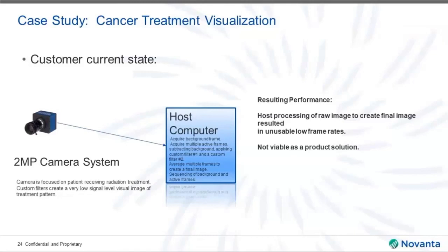And so there was a bunch of image processing algorithms that we did that were done first on the host computer. You acquire a background frame, you acquire multiple active frames of image data that include this signal that is a radiation and see where it's hitting the patient. You have to subtract the background frame and apply a couple of custom filters actually, and several operations in that. And those custom filters are there to reduce the noise. It's a very noisy signal, and to intensify the signal of the radiation, what you want to visualize. And then do some frame averaging again to reduce noise and to increase the signal level.